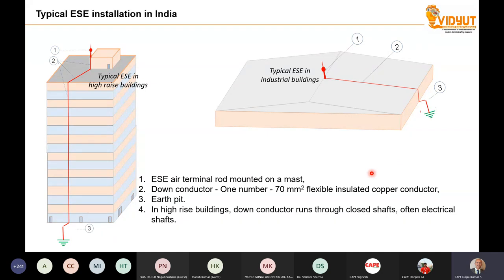And the danger again here is that in high-rise buildings, down conductors are always routed through some shaft, especially the electrical shaft. Along with the electrical wiring, the down conductors are also running. One of the classic examples is my own building. I live in an apartment, totally about 28 floors, about a 120 meter high building. There is an ESE rod at the top, the builder has provided it, and the down conductor is taken through the electrical shaft with a lot of bends.